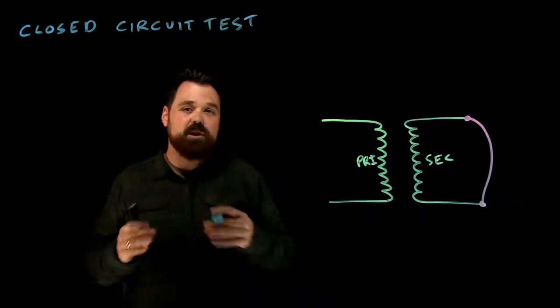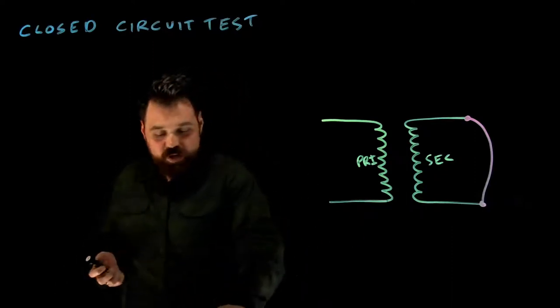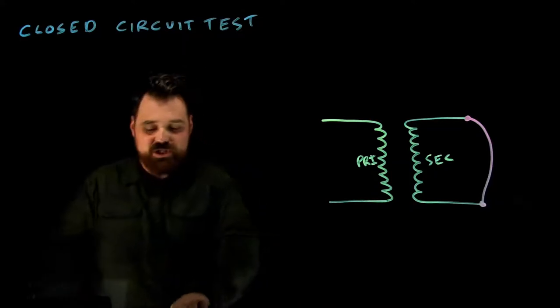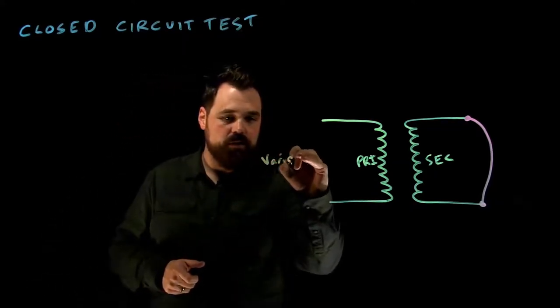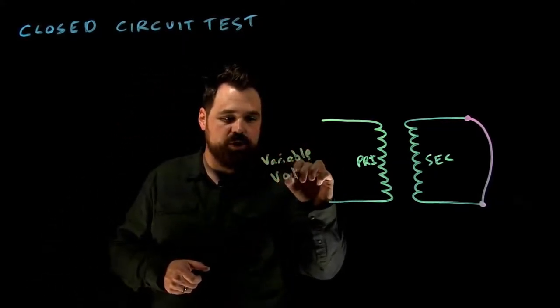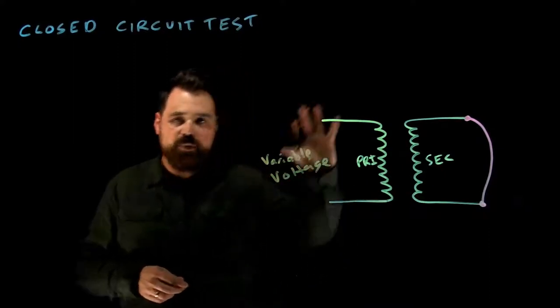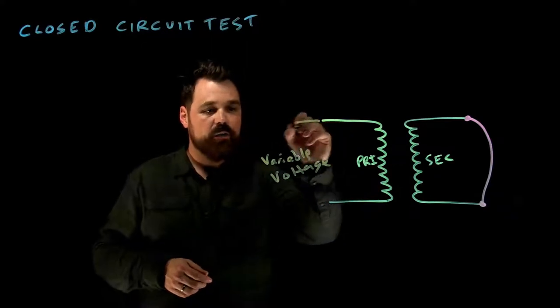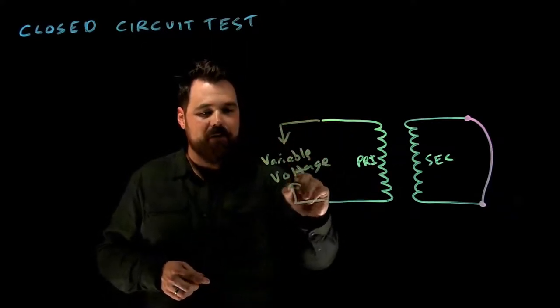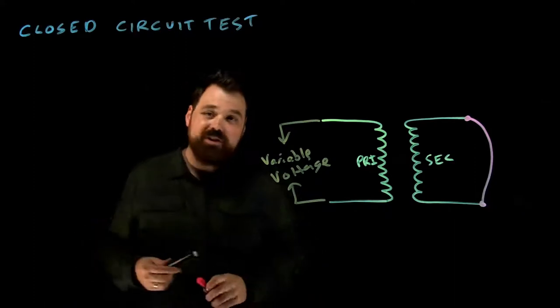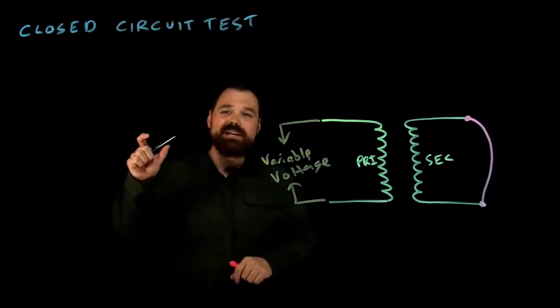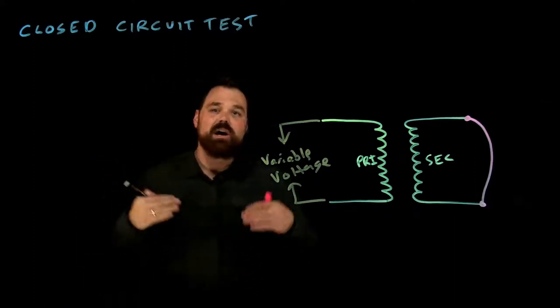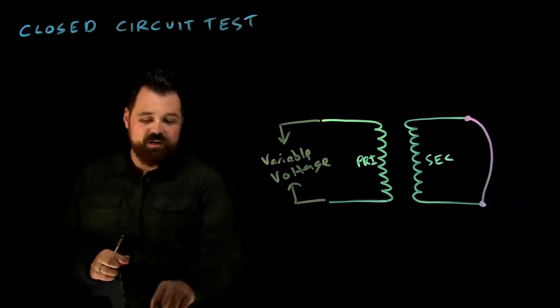What we're going to do with this closed circuit test is energize the circuit with a variable voltage. So we've closed-circuited the secondary, we've short-circuited the secondary, and we're going to connect up a variable voltage supply. We're going to slowly increase the voltage until we reach rated secondary current.